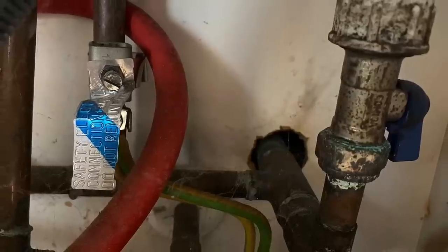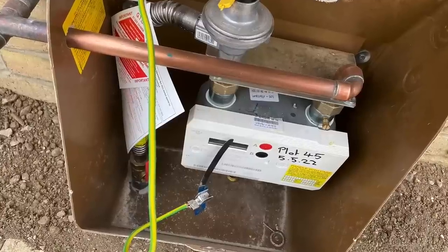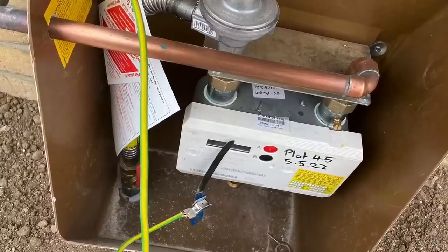It was only 6mm, but even so you'd still expect it to be massively low over a distance of probably a few metres from the consumer unit in the kitchen. You'd note that because it's been turned into a PME system, it's not necessarily adequate — the rules for PME require 10mm squared for bonding. However, the reading was acceptable. It's not always a necessity to change to 10mm squared. But I still see on social media what look like almost brand new installations still bonding the gas and the water.